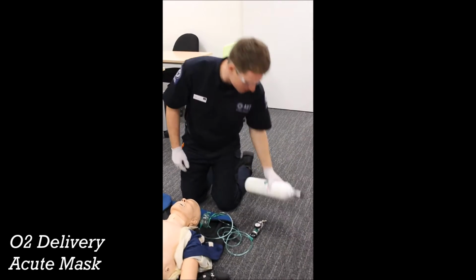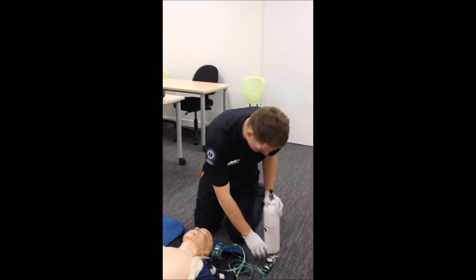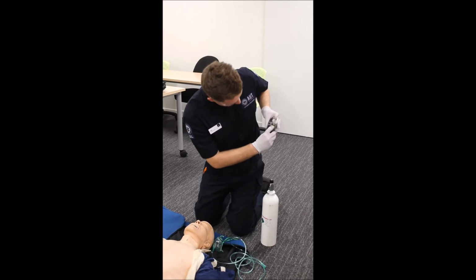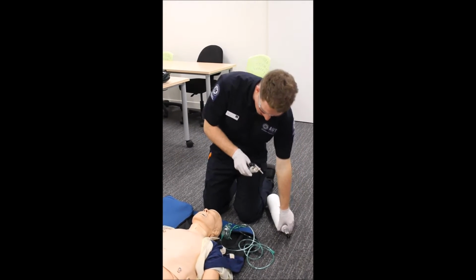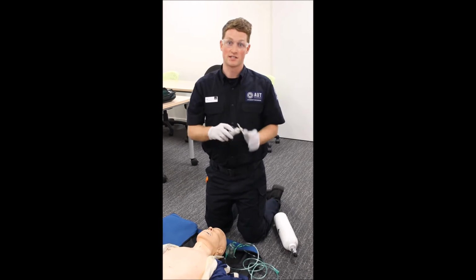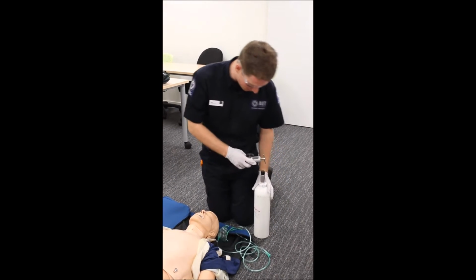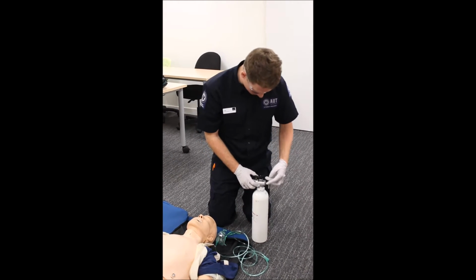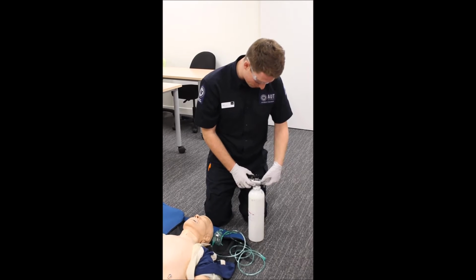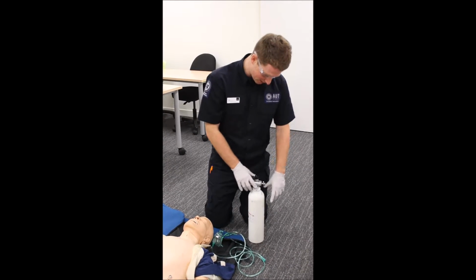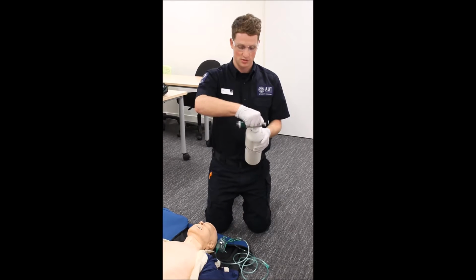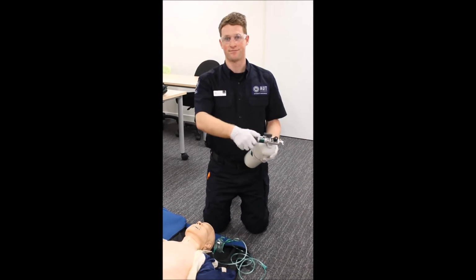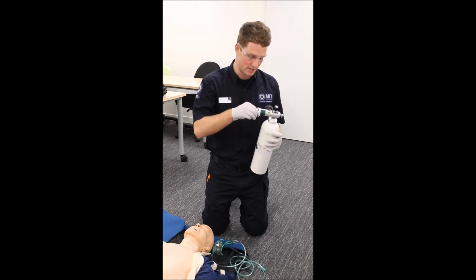Okay, so what we've got here is the oxygen tank, normally found in the back of the ambulance, and the oxygen regulator. First off we're going to check the Bodok seal, which is in the back there, just to check that it's a good seal, and it's going to create a nice tight seal to the oxygen. To put that on, we line up the prongs, slide it down and tighten the crank, and just as it goes in we quarter turn tighten it to show that it's connected. Then we open up the oxygen tank, which shows about half a tank, and test the flow rate. Yep, so that's still administering oxygen.